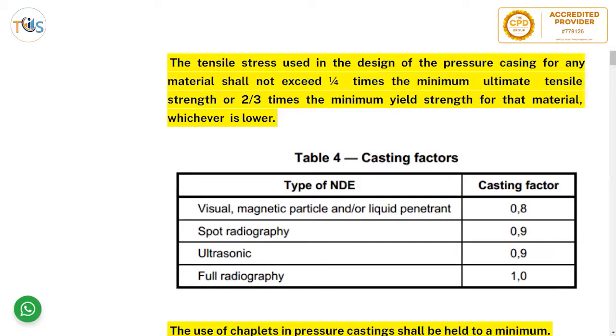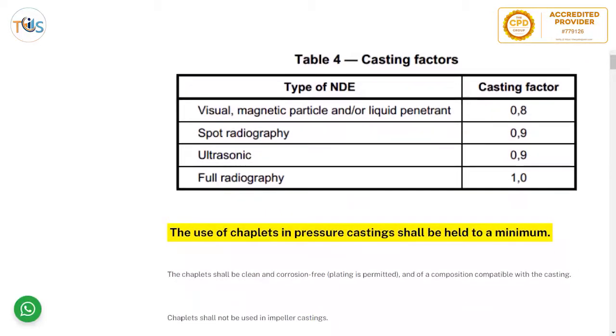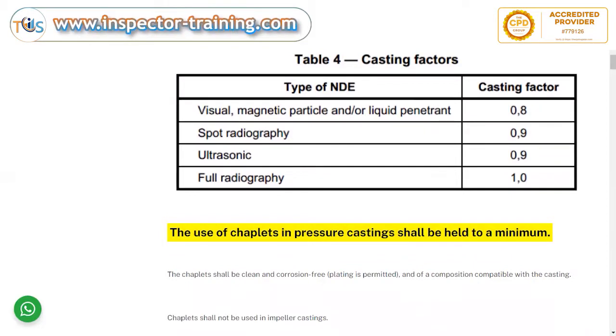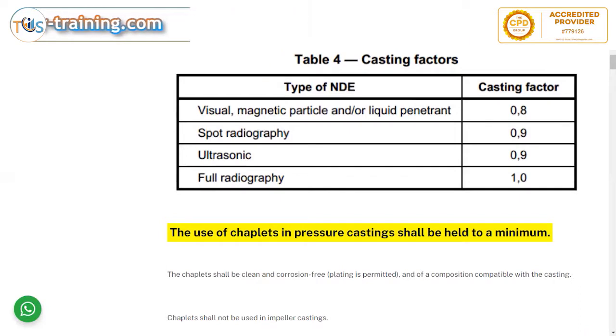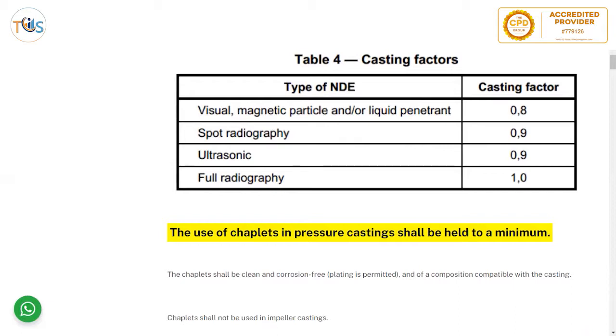Most pump casings are manufactured by casting because casting is easy — you can make any shape, there is no wastage of material compared to machining, and it is one piece, which is very important especially when the pump is under fatigue load and constant vibration. Similar to joint efficiency for welds, castings have a casting efficiency factor called EC.